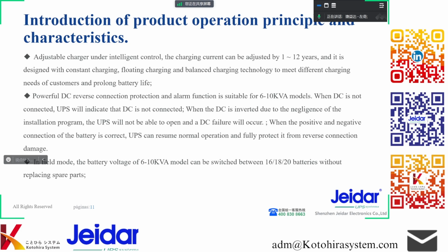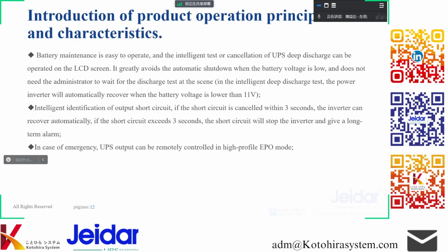In field mode, the battery voltage of 6 to 10 kVA model can be switched between 16, 18 and 20 batteries without replacing spare parts. Battery maintenance is easy to operate, and the intelligent test or cancellation of UPS deep discharge can be operated on the LCD screen. It greatly avoids the automatic shutdown when the battery voltage is low, and doesn't need the administrator to wait for the discharge test at the same time. In the intelligent deep discharge test, the power inverter will automatically recover when the battery voltage is lower than 11 volts.